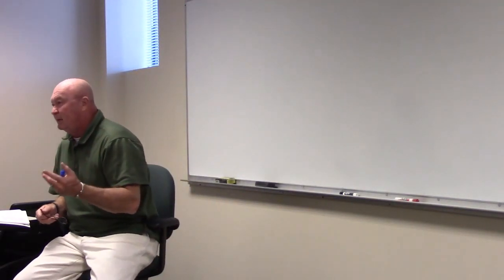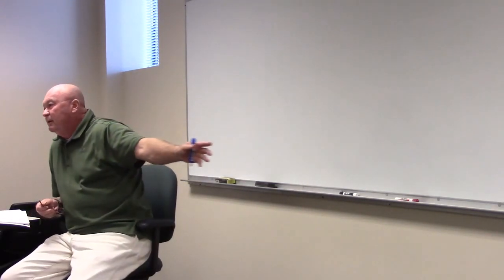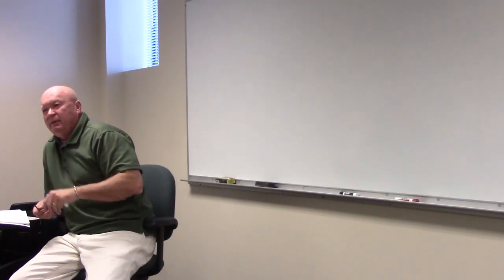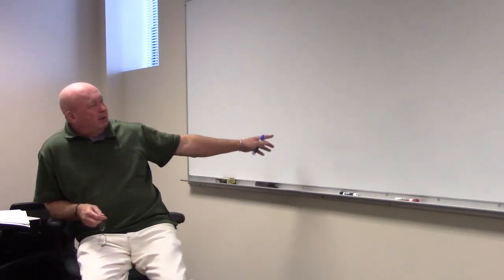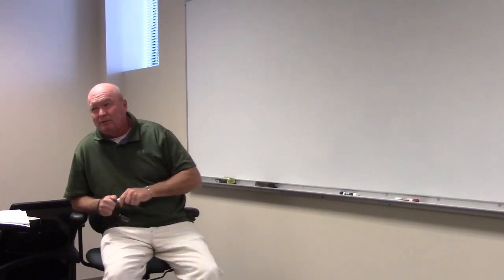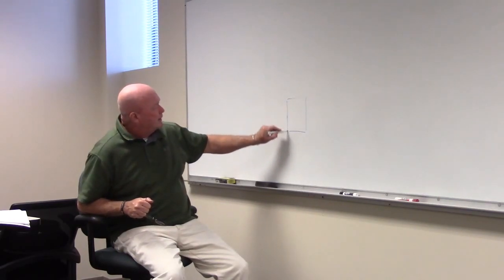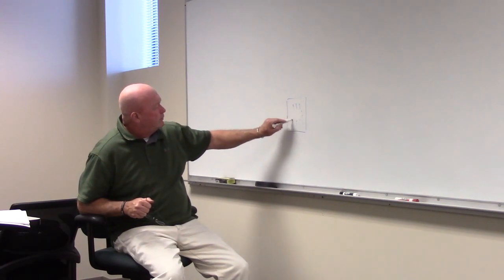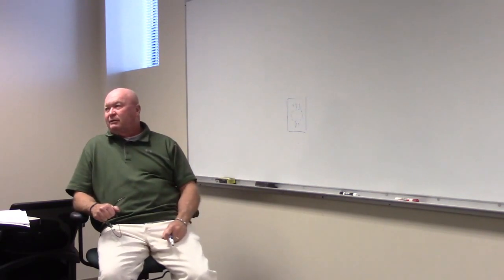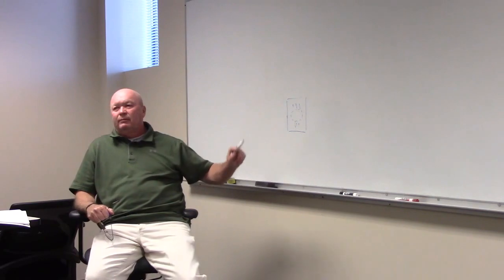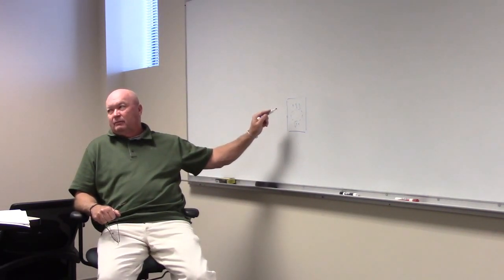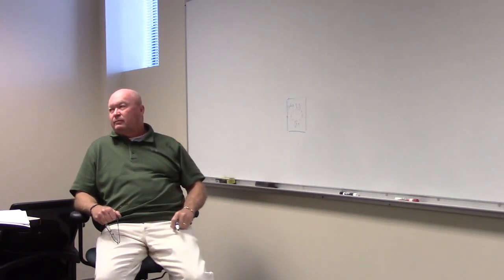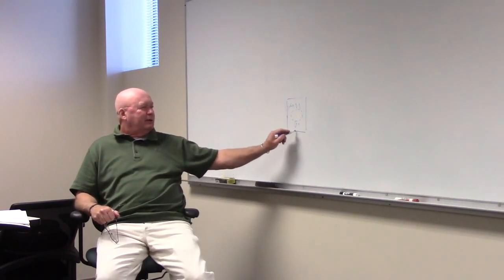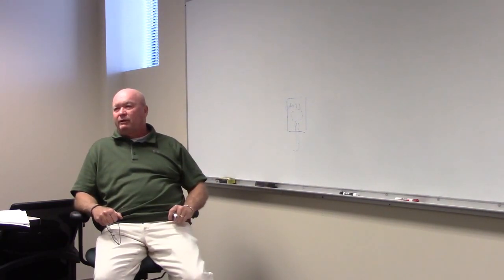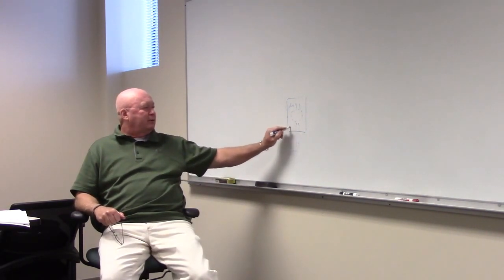Okay, so let's look at our definition there. And it is the load side, right? Because the line side of that meter is what? It's the power company, right? The load side is typically something we're bringing in. And again, down this meter, whether it's overhead or underground, it's something to think about too, because I think people do this wrong. Alright, so this meter, inside of it, you got, which is the load side and the line side? Line side would be top, regardless whether it's underground or overhead. Y'all agree? That's the line side regardless. I've seen people bring in underground wires and hook them right there. Seen it more often than not. Okay. But this is their load side regardless, isn't it?